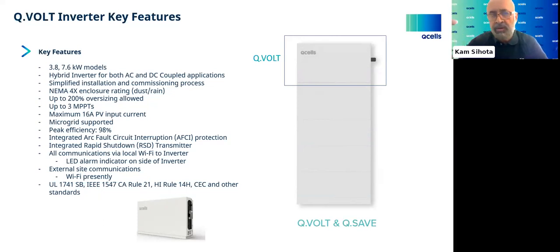If you need an RSD, rapid shutdown, we provide that - the inverter has a built-in rapid shutdown transmitter. Or if you have a special case where you need optimizers, we have a solution for that paired with this system, tested and deployed. There's no monitor or display on here, so that's where your smartphone or handheld device comes in. You walk up to the inverter, connect to the local Wi-Fi, scan the barcode, update the firmware, create the settings and operating mode, and off you go. All the safety standards you need for North America - that's the solution.